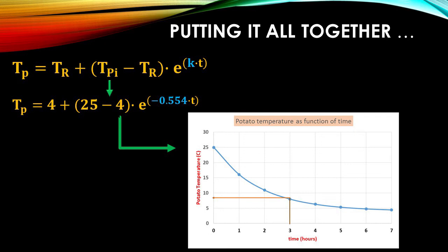Okay, so say the product temperature that's required is 5 degrees. Say after 3 hours, you want to check whether it has reached 5 degrees. So you just go to your 3 hours and you read across your temperature. It's about 8 degrees, so it's not good enough. Okay? So that's how you use it. So here is its usefulness.